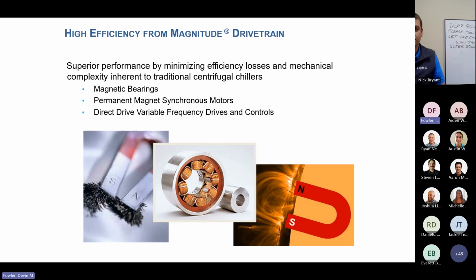We're going to offer a permanent magnet synchronous motor versus a traditional AC motor. This will be a direct drive machine with variable frequency drives and some complex controls that can give us better efficiency and better operating points as well. We don't have to worry about having gears in our system, taking an AC motor and using the gear drive to speed that up. Everything's going to be done through the VFD.